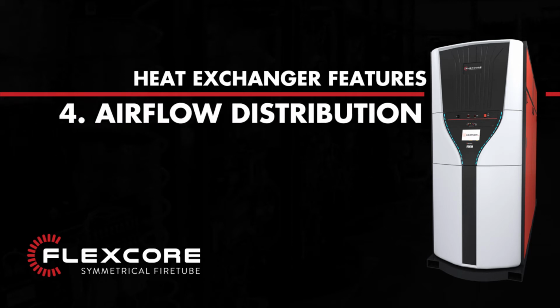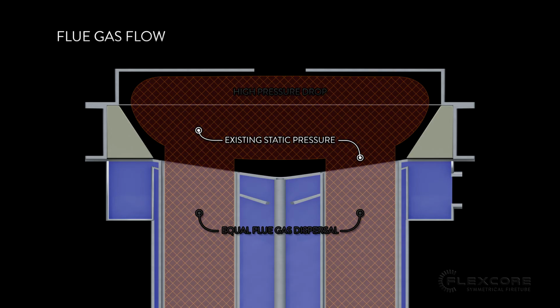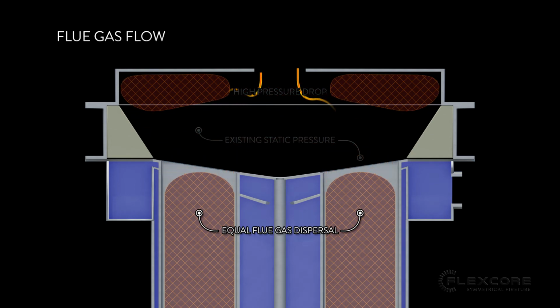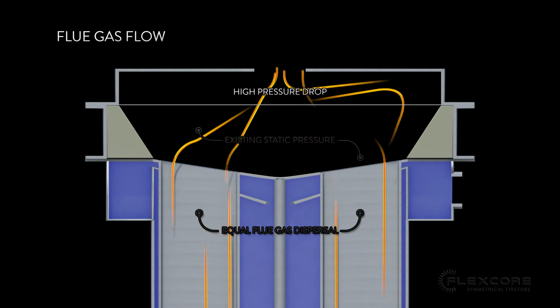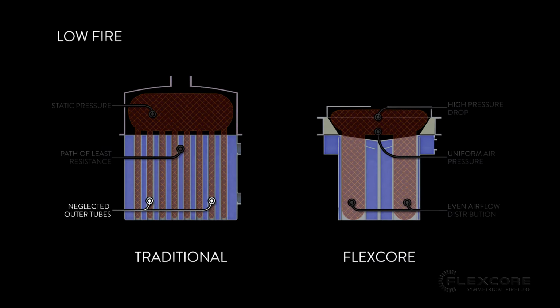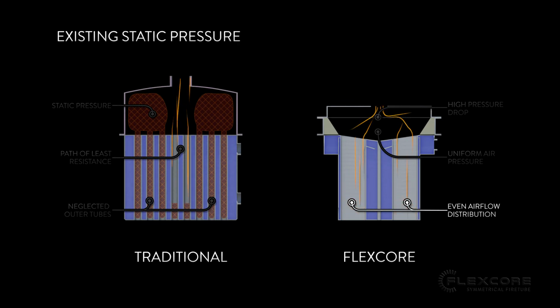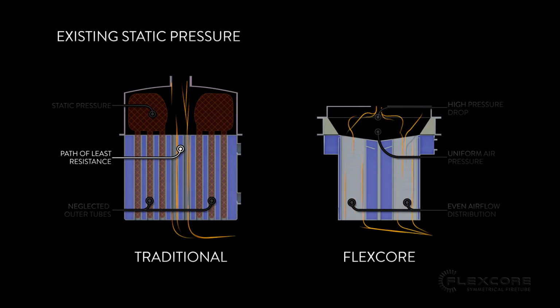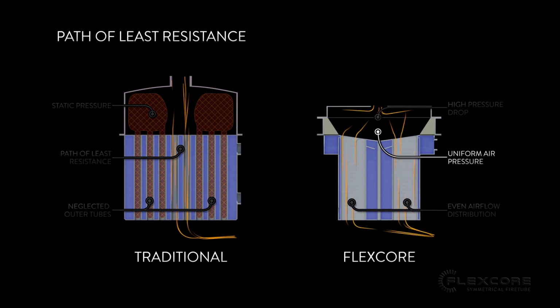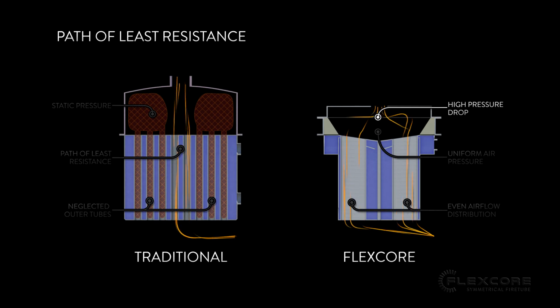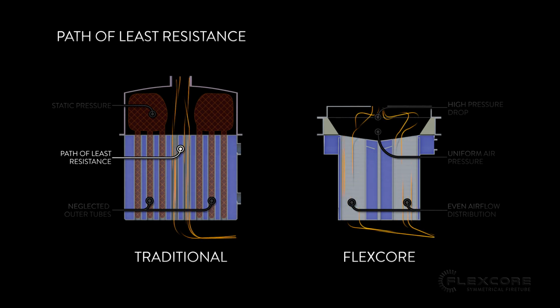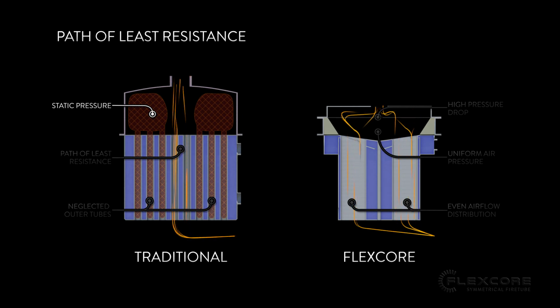4. Even airflow distribution. The Flexcore's heat exchanger has been designed to allow flue gases to flow down each tube equally. A traditional heat exchanger's tubes can get neglected around the outside of the crown sheet, because the flue gases aren't getting dispersed and are following the path of least resistance straight down the middle. This is especially important when the boiler is in low fire. This is because the incoming flue gases will be under lower pressure. In a traditional heat exchanger, the flue gases would tend to stick even closer to the path of least resistance due to the existing static pressure in the combustion chamber.